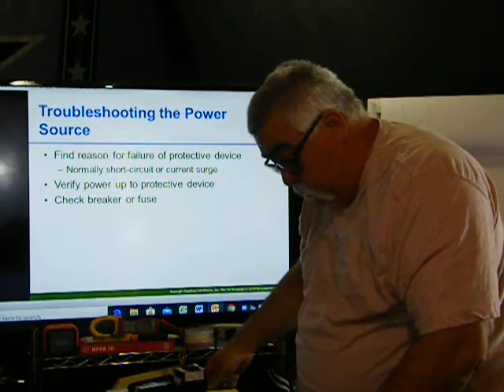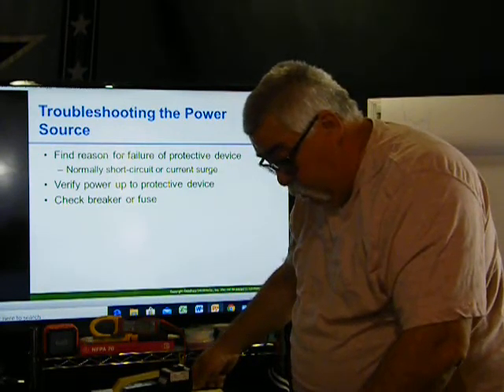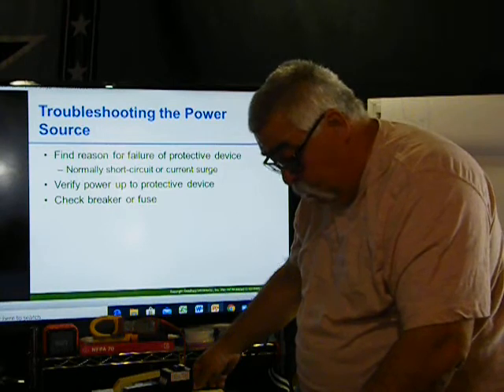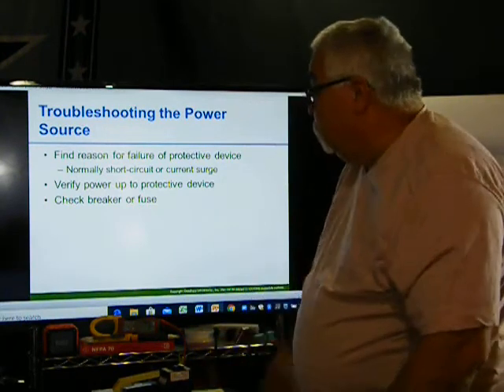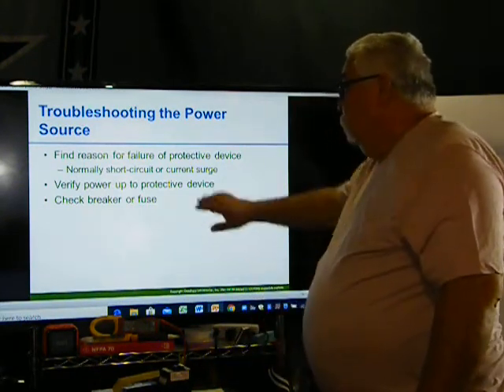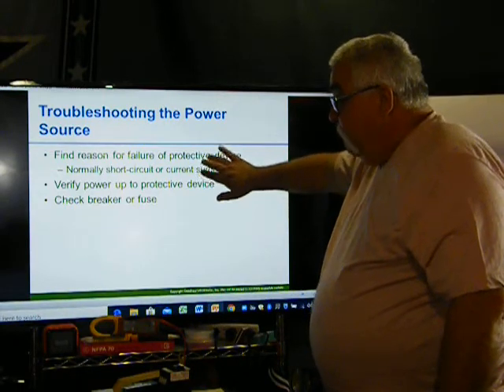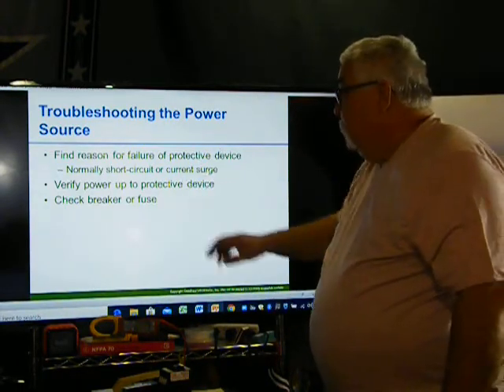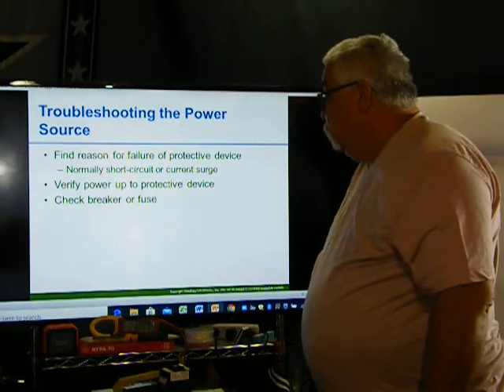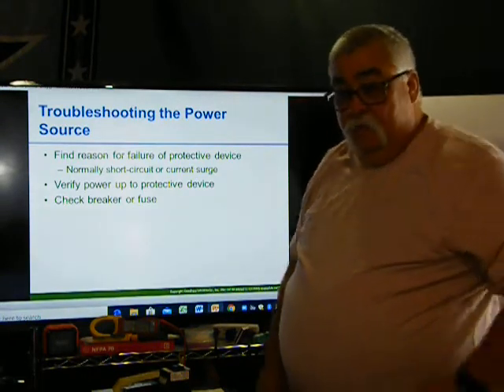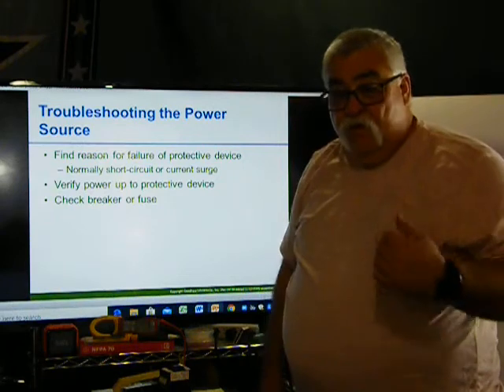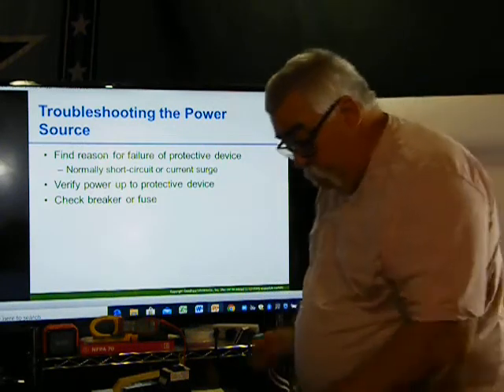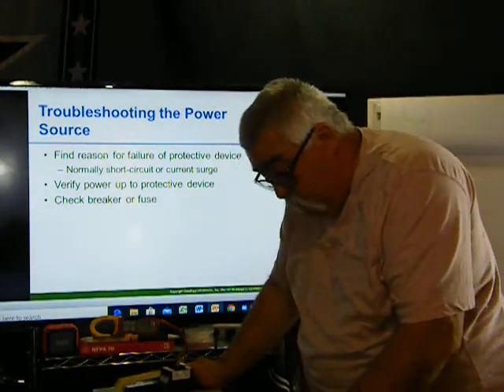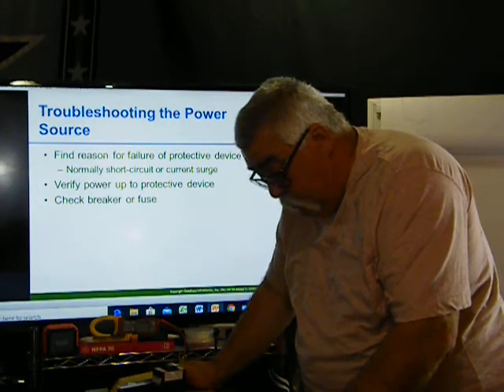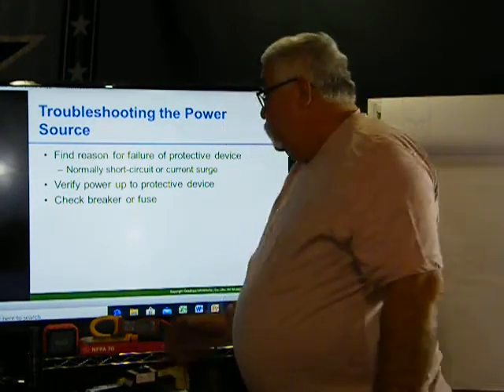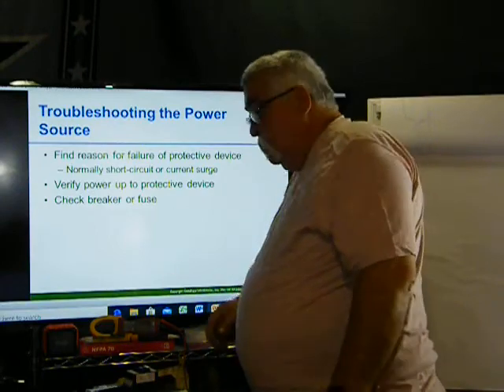The failure is normally a result of a short circuit or a current surge, but it must be investigated and resolved before replacing the breaker or fuse. So make sure you figure this out. Find the reason for the failure of the protective device, normally a short circuit or current surge. What caused it, before you do it. Even before checking, make sure there is power up to the protected device. So verify that power is at the protected device.